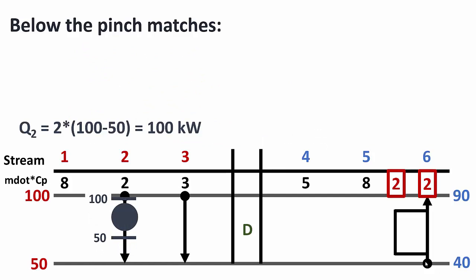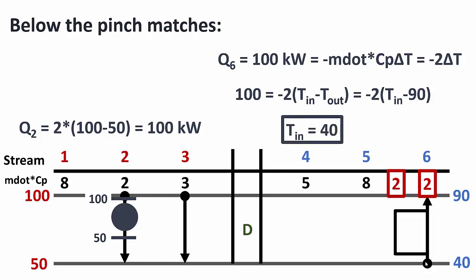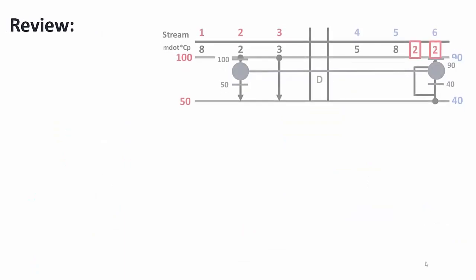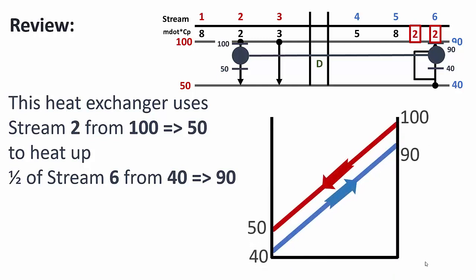Stream 2 has Q = 100 kW. We transfer 100 kW to one half of stream 6: 100 = −2 × (T_in − T_out). The negative sign is important. Starting from the top, we specify T_out = 90°C and solve for T_in = 40°C. This heat exchanger uses stream 2 from 100 to 50°C to heat up one half of stream 6 from 40 to 90°C. The temperature graph confirms the minimum approach temperature is not violated.